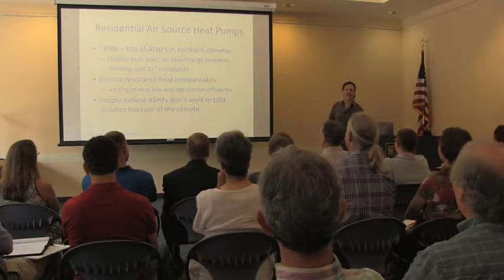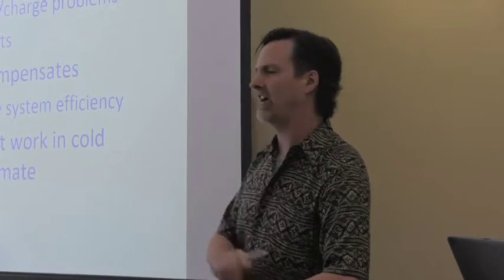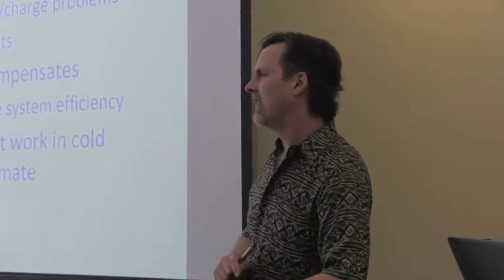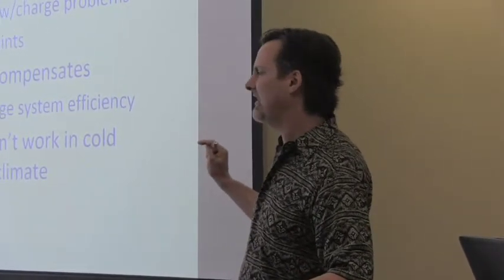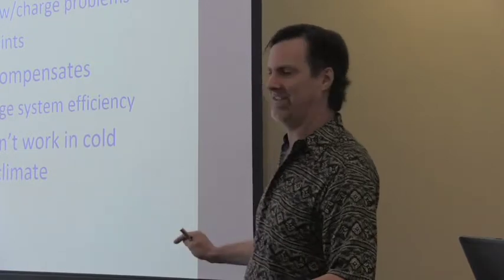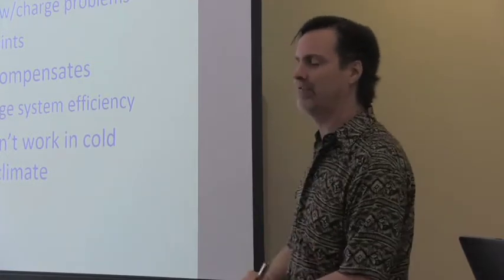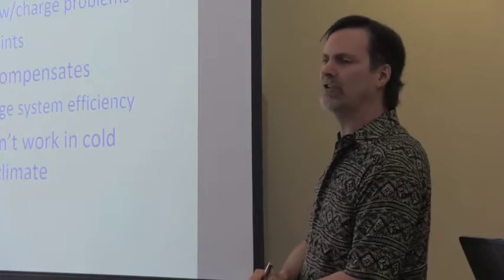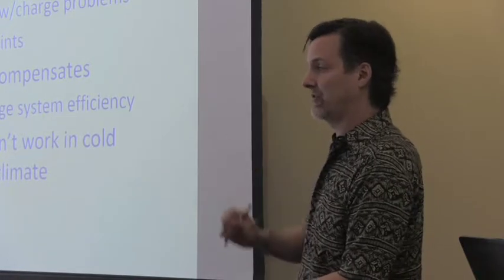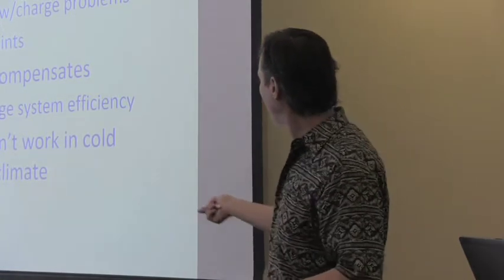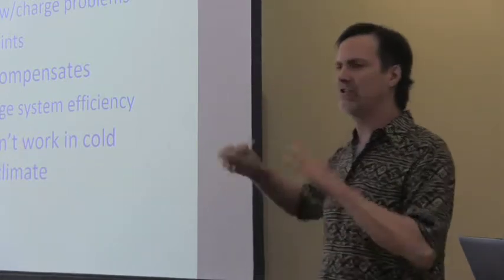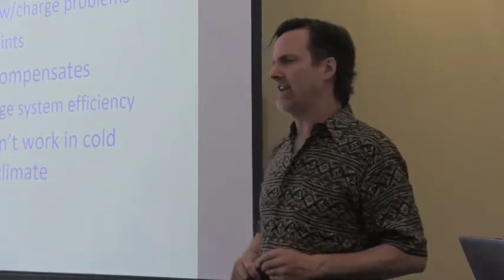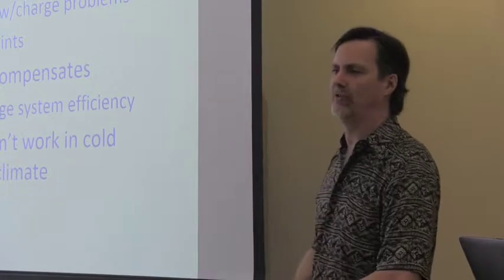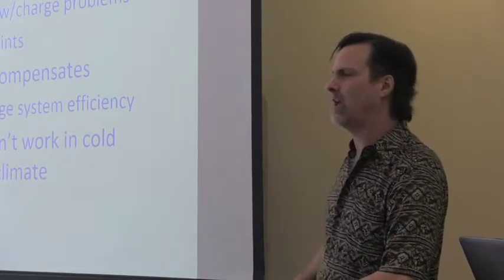In the Pacific Northwest, they did a study in the 80s, and they actually found that heat pump heated houses used more electricity to heat than electric resistance baseboard heated houses, even though theoretically the efficiency was something like 2 to 2.5 times as much. They actually used more energy. So basically, this led to a widespread belief that air source heat pumps don't work in cold climates. It wasn't because the climate was too cold.